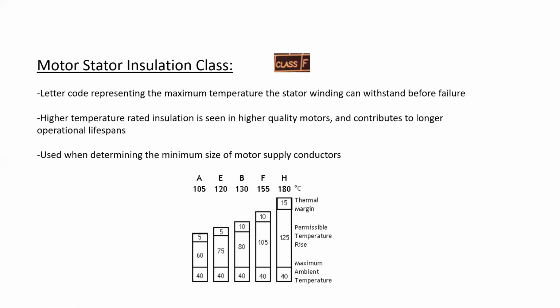You do not have to memorize what the exact temperatures are for each one, but you do need to know that A is the lowest temperature and therefore used in the cheapest motors. B is the most common insulation class for 3-phase motors. And H is the highest temperature insulation rating, and it's used in more expensive motors, as well as motors that are intended to be used in very high temperature environments.